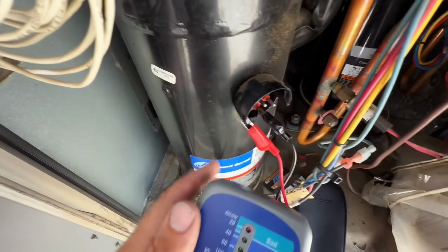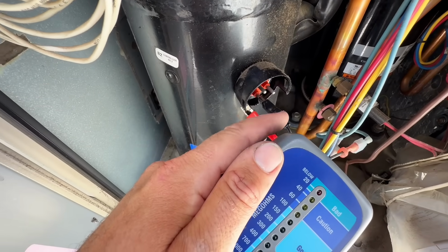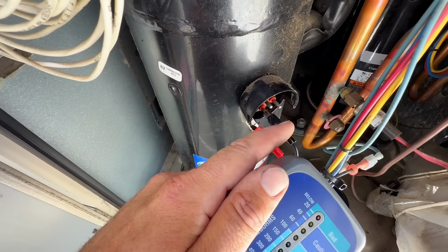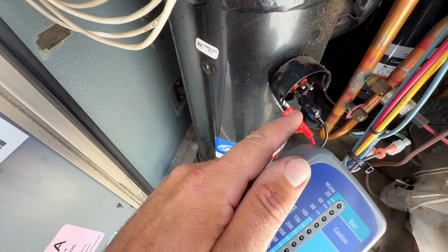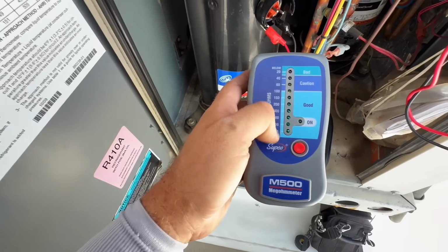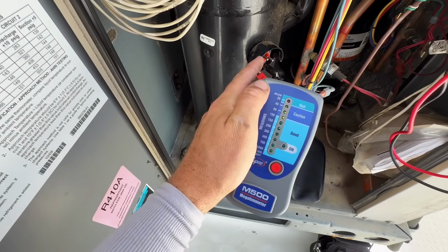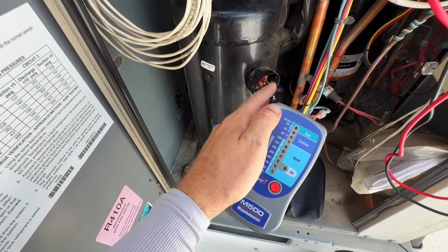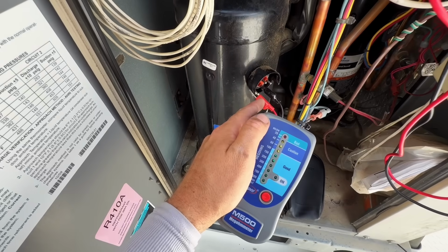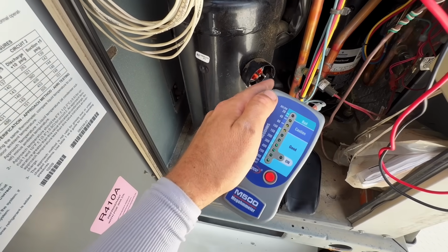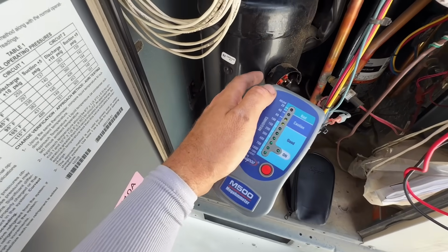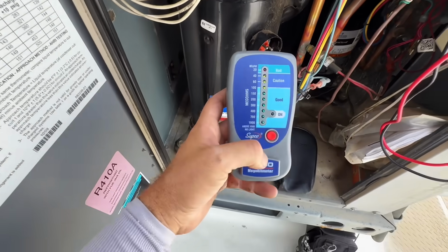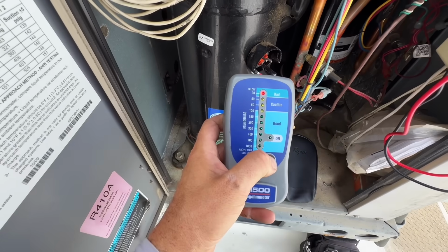When you are connecting and testing your insulation to ground, you want to put one side onto your terminal and the other one connected to ground. And then what it does, when you click the button, it sends voltage in here and it sees if the voltage comes back to the other terminal, and that will tell you that the insulation is bad, because you're not supposed to have any voltage leaking out of your windings. But let's push the button and see what it tells us.